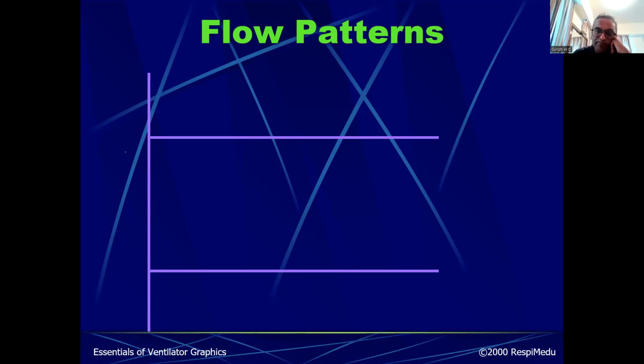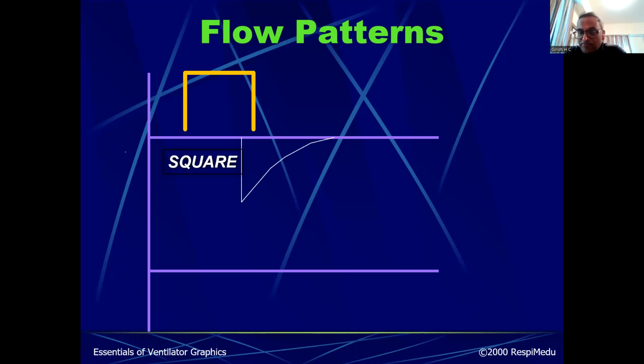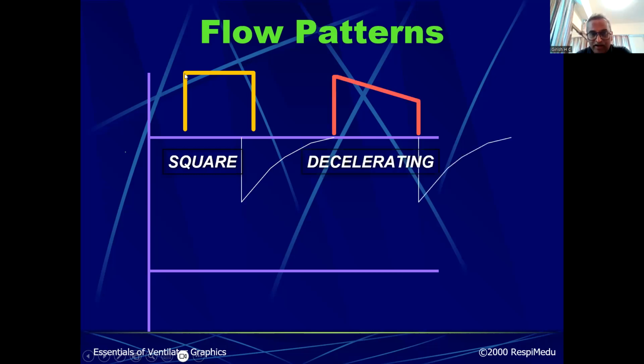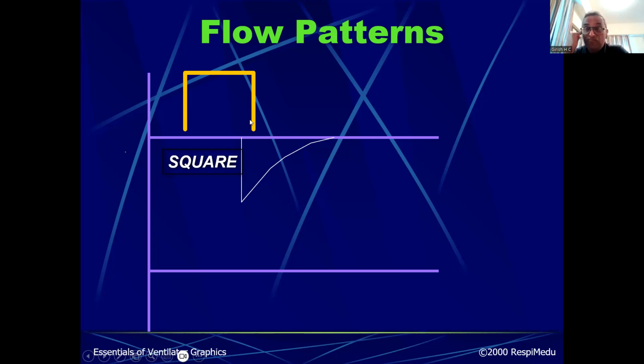So when you talk about a particular type of breath given to the patient, you're talking about what type of flow it is. So there are various types of flow. This is a square wave flow. Square wave in the sense, see, your x-axis is time and y-axis is flow. So the flow goes up and then it remains constant and it goes down. So this is what the volume ventilation does, because volume can be measured if the flow is constant. So flow multiplied by time, you know that it is volume. So in a volume ventilation, always the flow is constant flow, so that then you can easily calculate the volume given to the patient. So the square wave is always the volume ventilation.